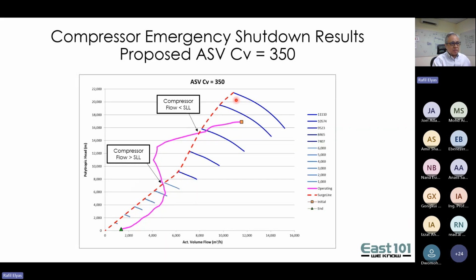So we've tried this analysis. If you take a look at this map, this is essentially a multi-speed compressor, and this is the initial operating point. Upon shutdown, you can see it starts to wind down. The speed starts to reduce and the flow starts to reduce accordingly. This red line here is the surge limit line. Once you go into the surge limit line, you're at risk of the compressor going into surge. You can go into the negative flow region, go back and forth, and that causes your vibration. So we want to keep it away from this red line.